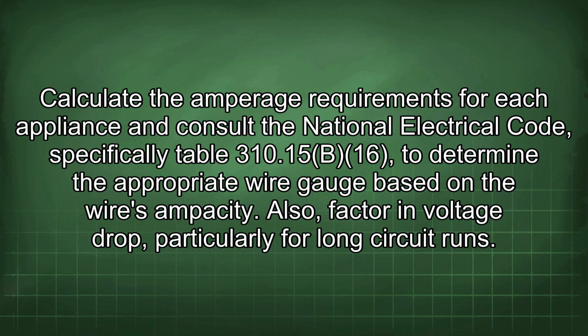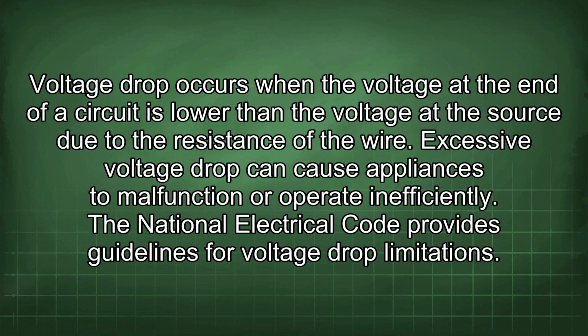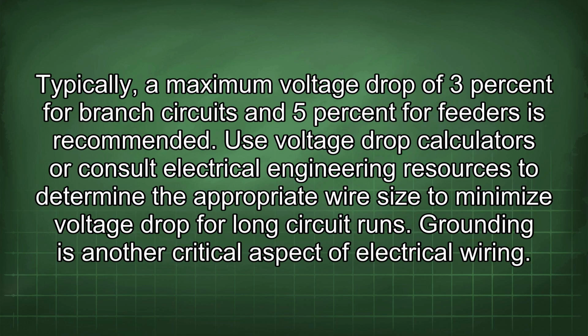Also, factor in voltage drop, particularly for long circuit runs. Voltage drop occurs when the voltage at the end of a circuit is lower than the voltage at the source due to the resistance of the wire. Excessive voltage drop can cause appliances to malfunction or operate inefficiently. The National Electrical Code provides guidelines for voltage drop limitations. Typically, a maximum voltage drop of 3% for branch circuits and 5% for feeders is recommended.